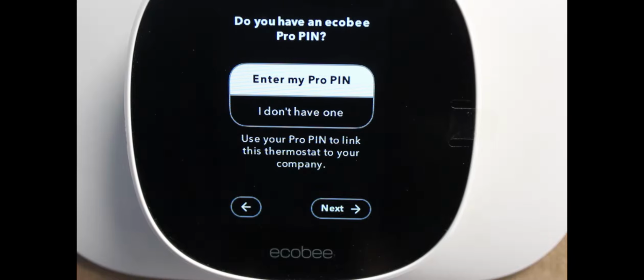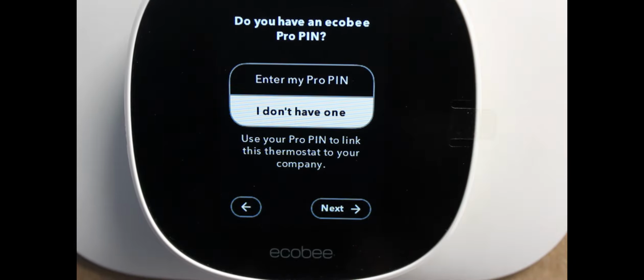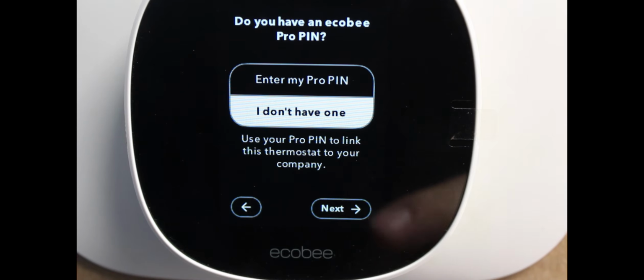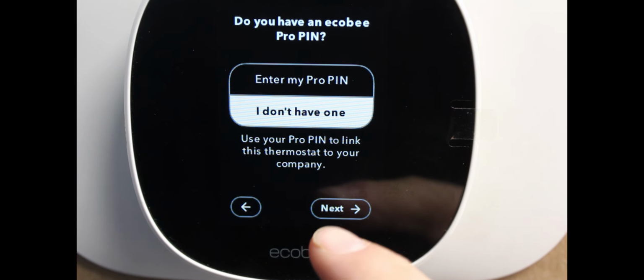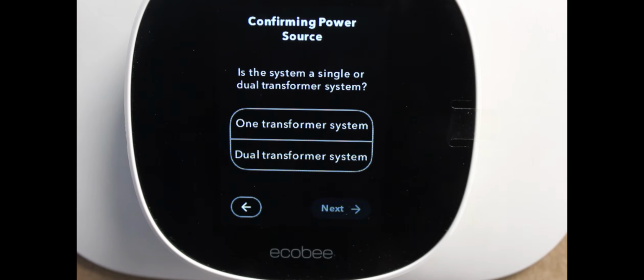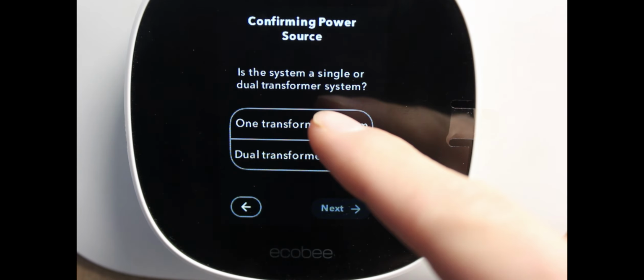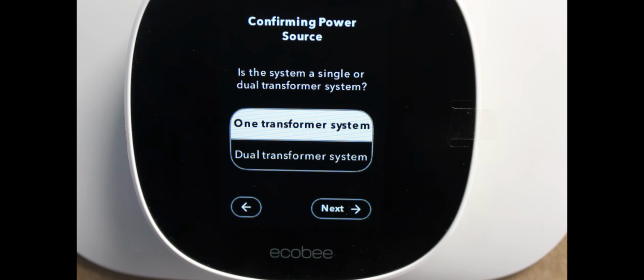It's going to ask for a pro pin. We don't need to have one. That's just a way to link this thermostat directly to your company. And then it's going to ask for your power source, one transformer or two. Almost every system we install is going to be one transformer. The only application where you should be selecting two or dual transformer system would be if you have one thermostat that's controlling both a boiler for heating and then say a separate air handler for the cooling.